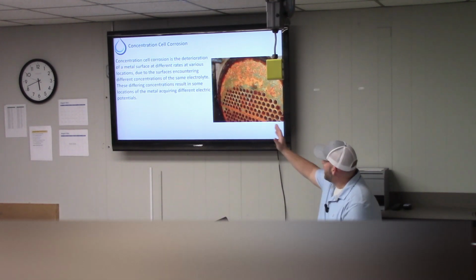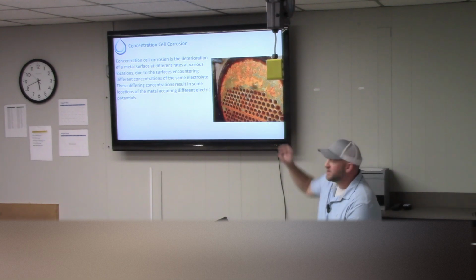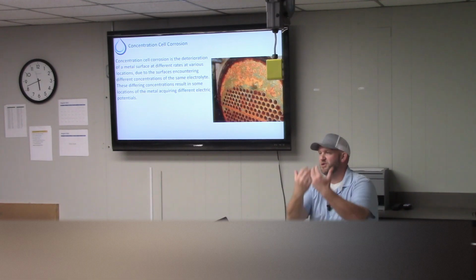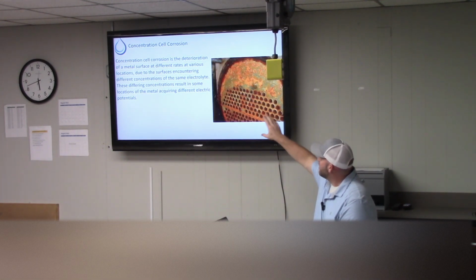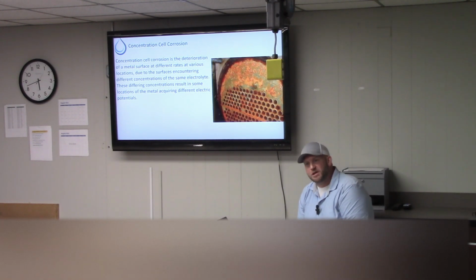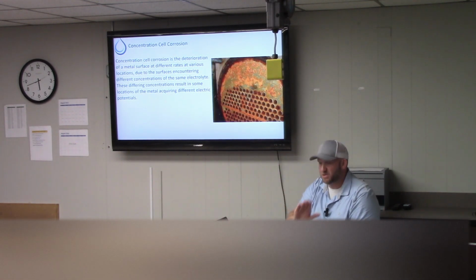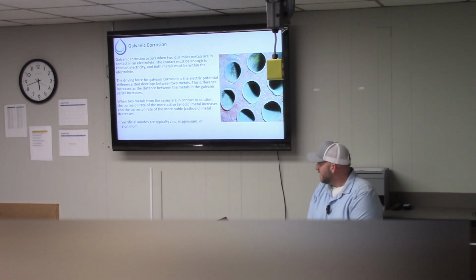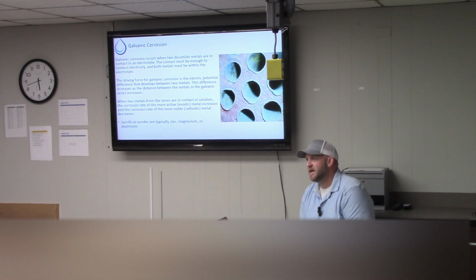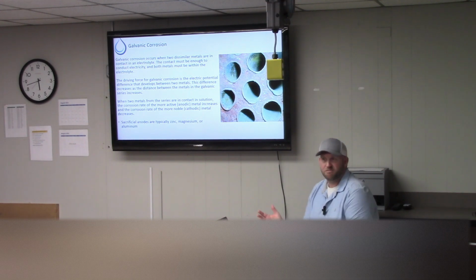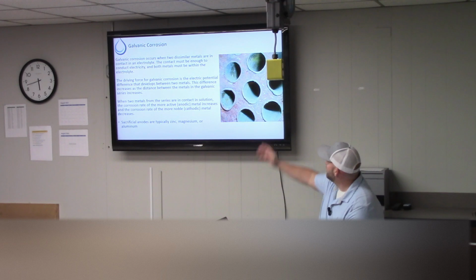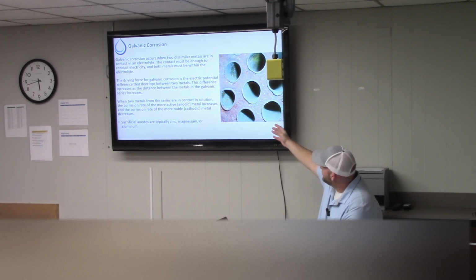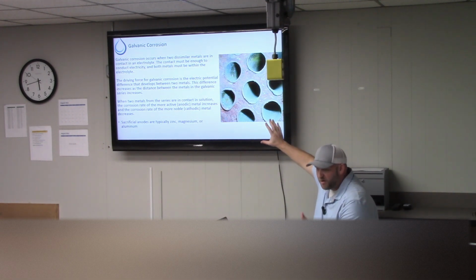And as a result, in some spots where you have lower flows, or you have different concentrations of the same medium, water, but maybe it's a little more cycled there than it is here, this is going to exist, and why you will find, when you take the bell end of a chiller off, you see different depths of this corrosion, of that corrosion, oftentimes it's related to this. The other thing that it could be related to, the reason for these pouty lips on these particular chiller tubes, is galvanic corrosion. If the water chemistry does not support inhibiting the corrosion of both yellow metal and ferrous metal, mild steel, the way that it should, then you run the risk of having corrosion and dissolution of the copper and the steel, but right now we're going to focus on the copper.